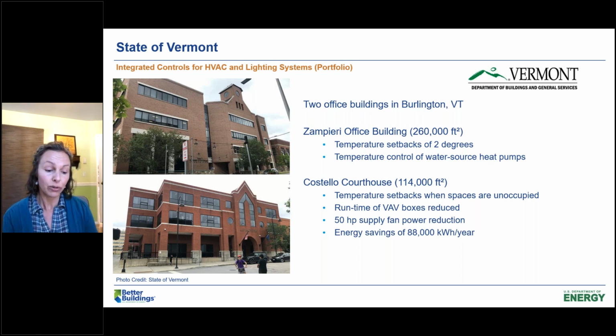The advanced lighting controls integrated with BMS via BACnet allowed them to set temperatures back in unoccupied spaces, as well as control the water source heat pump temperatures, reduce the runtime of the VAV boxes, and also reduce the fan power for the 50 horsepower supply fans. And all of this yielded 88,000 kilowatt hour savings for Costello Courthouse alone.